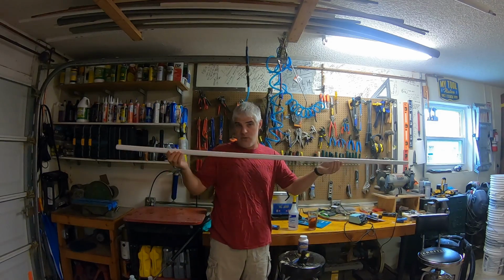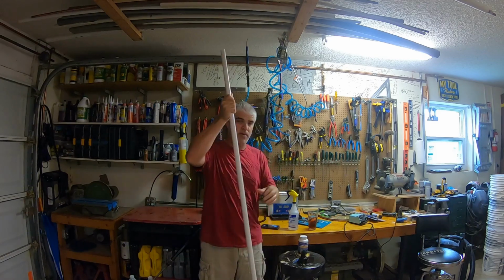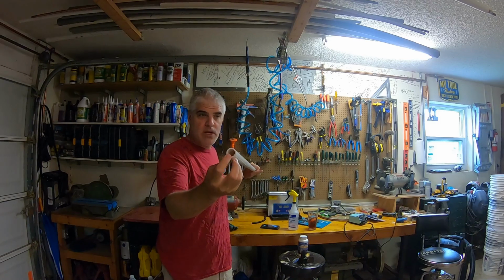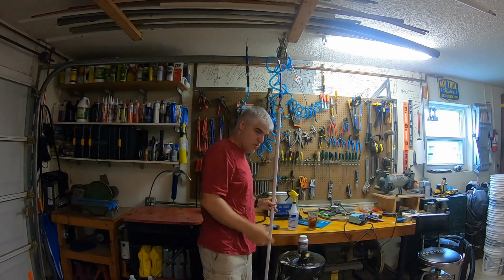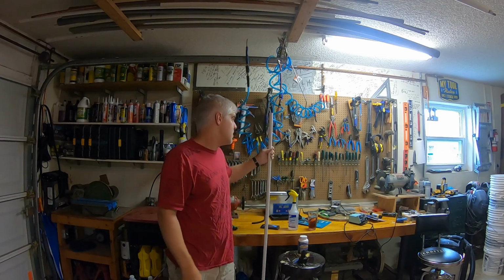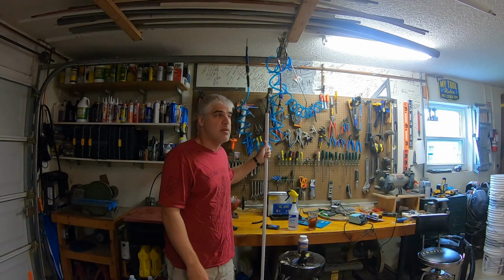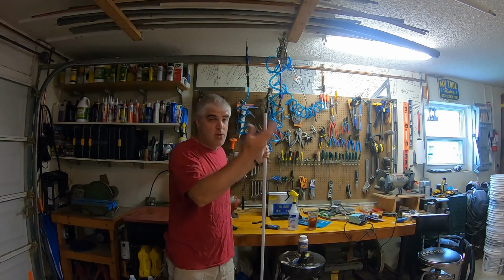just like this. It's a Schedule 40 3/4 inch PVC. And over time, the inside of this pipe, well, this is just a demo, but the inside of this pipe will be clogged with stuff that kind of resembles snot. It's bacterial growth, fungus, whatever grows in these things. So over time, that will cause the system to back up, and if you are lucky enough to have a float switch, the unit will shut off.